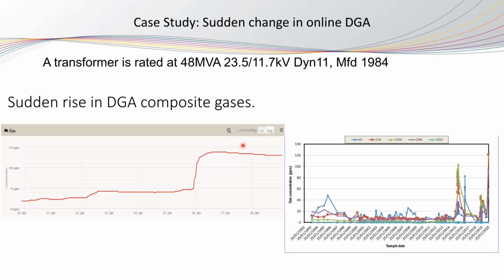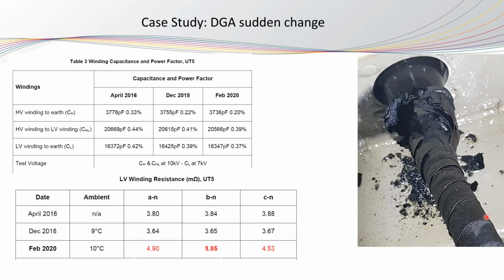And the second step with the online data, when it shows that there are abnormalities, they decided to take an oil sample. With an oil sample, we are speaking about in-service testing. When they did the sampling, they found that the value of the overall composite gas was quite high compared to the previous one. So at this point, the client decided to take the transformer out of service for the offline testing.